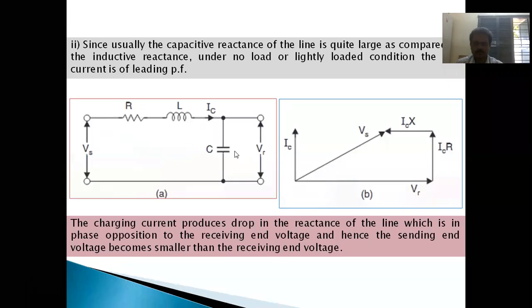Here, resistance is more, capacitive reactance or capacitive susceptance is more when compared to inductive reactance. Under lightly loaded condition, we can also eliminate the resistance value, so we can neglect resistance under no load conditions. So here inductive reactance value is less, this is more, and that's why the receiving end voltage always becomes more when compared to sending. Is it clear?